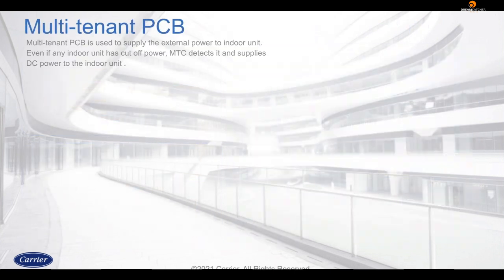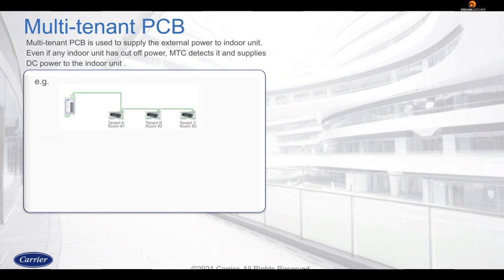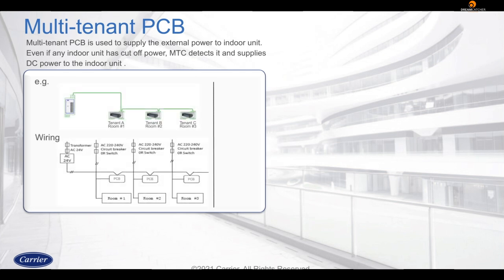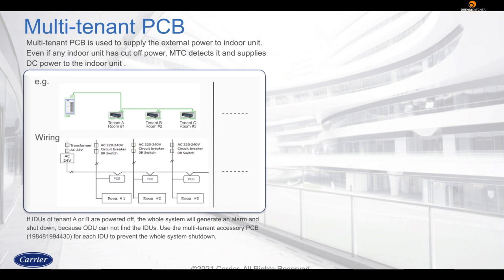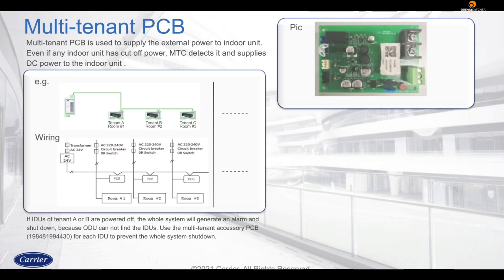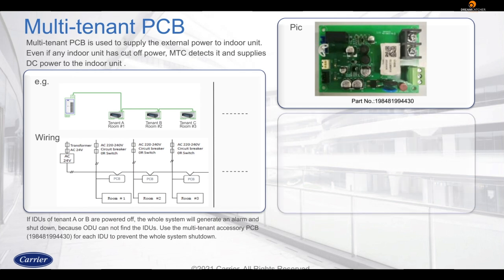The multi-tenant PCB works in a scenario where tenants in a service apartment are away for a certain period and have to power off the indoor unit, which is part of the system that is still running. To prevent the whole system from being cut off, the multi-tenant PCB is responsible for that. If any indoor unit faces a power cut, it supplies it with DC power. This is especially useful in setups with different rooms, as any single room power failure would result in a complete system shutdown. But the multi-tenant PCB ensures that such a scenario does not arise by supplying power to the IDU.